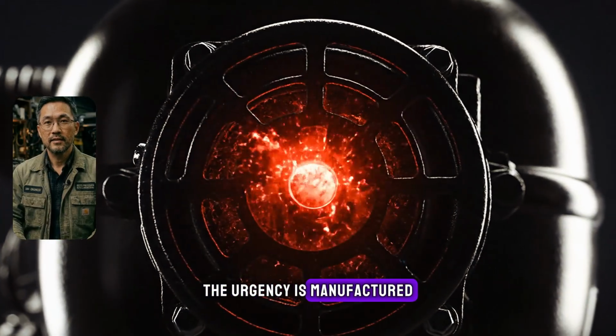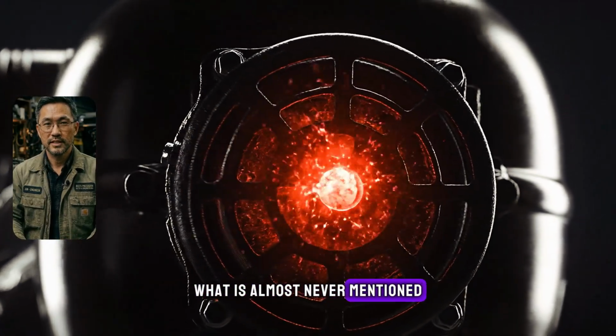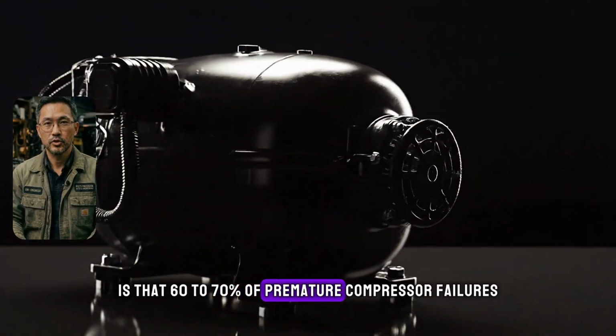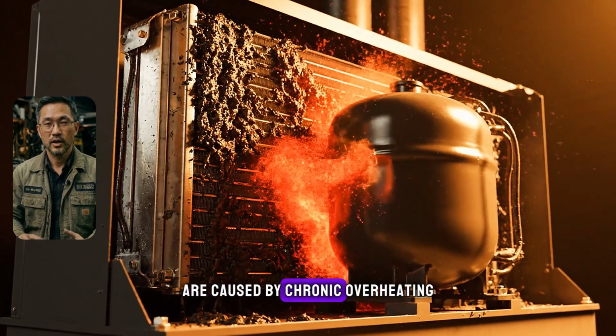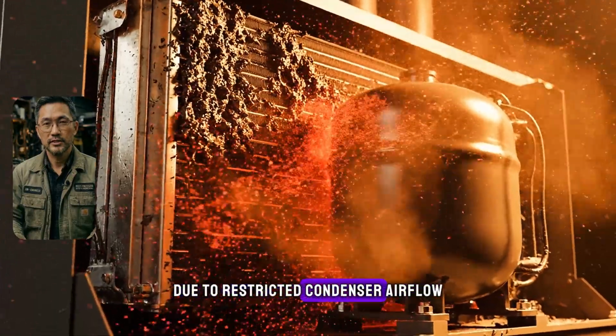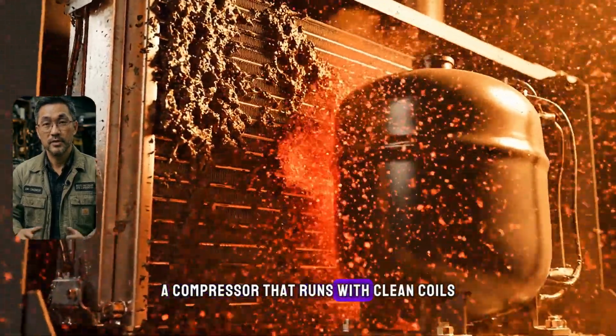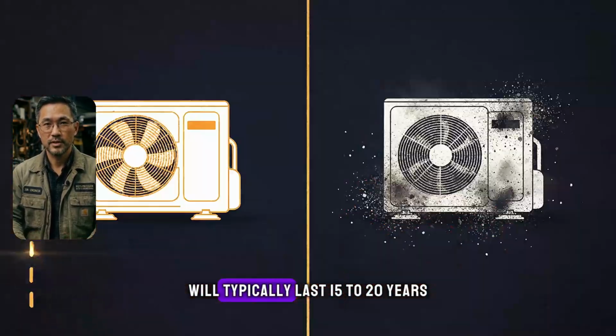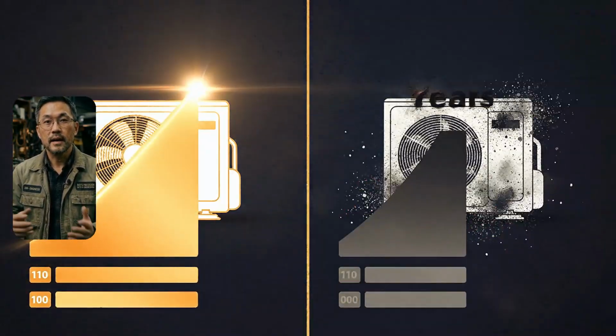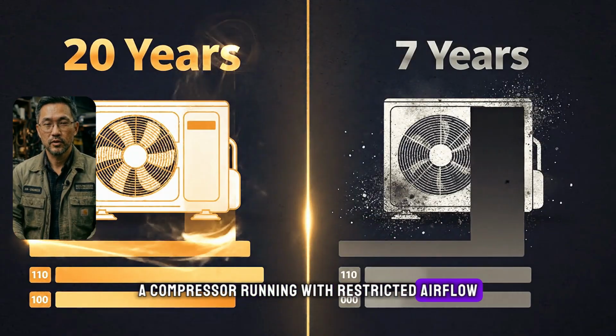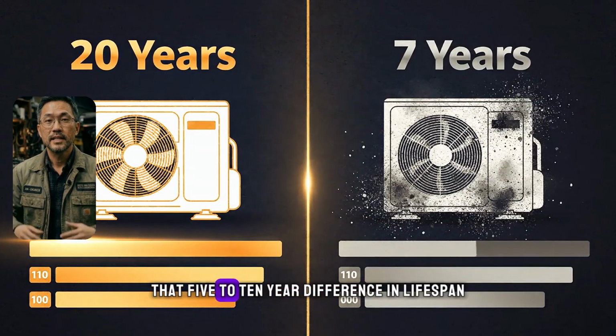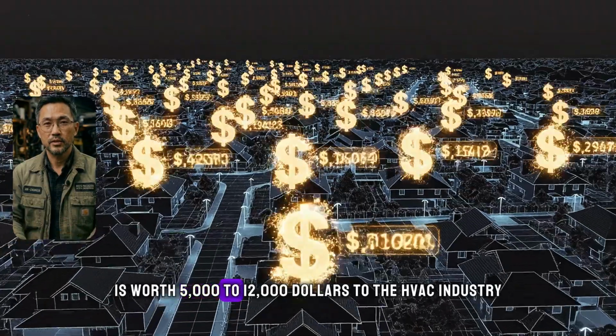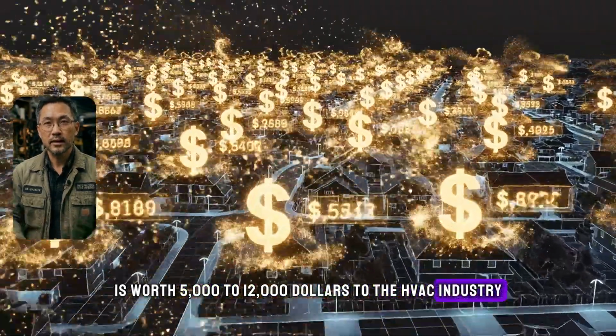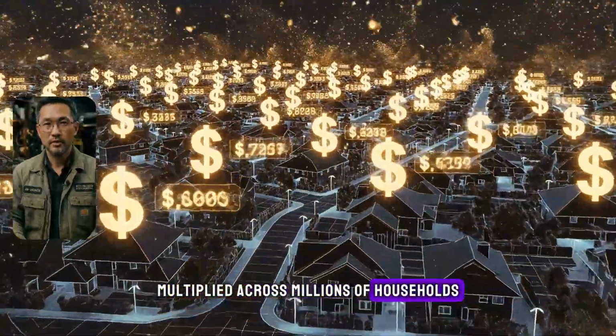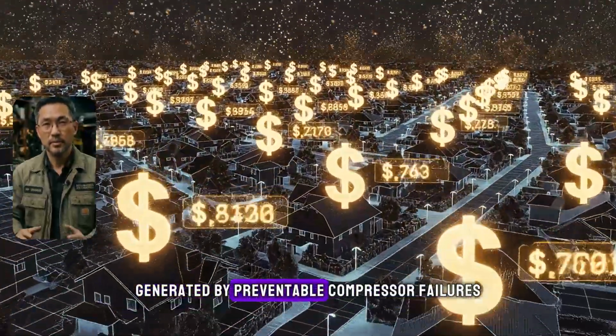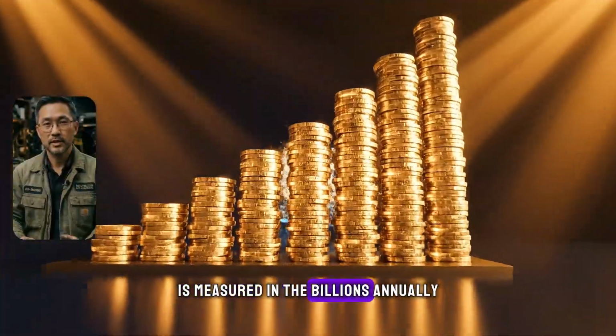The urgency is manufactured. What is almost never mentioned is that 60 to 70% of premature compressor failures are caused by chronic overheating due to restricted condenser airflow. A compressor that runs with clean coils and adequate airflow will typically last 15 to 20 years. A compressor running with restricted airflow fails in 7 to 10. That 5 to 10 year difference in lifespan is worth $5,000 to $12,000 to the HVAC industry. Multiplied across millions of households, the revenue generated by preventable compressor failures is measured in the billions annually.